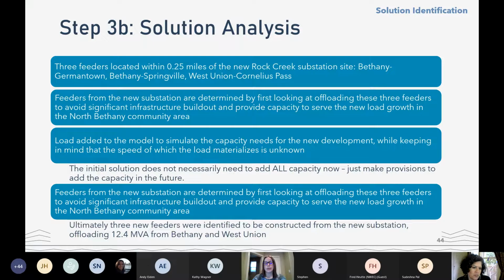Even when we don't know exactly where the load is, we can add spot loads to the model to simulate the new load being added to the system. The speed at which load materializes is somewhat unknown; we have insight into when houses start being built, but those plans regularly get delayed. So we didn't need to add all the capacity immediately, but we needed to make provisions to add capacity in the future, since we didn't want to build a substation for just a small immediate load and then have to build another one or expand that substation later.